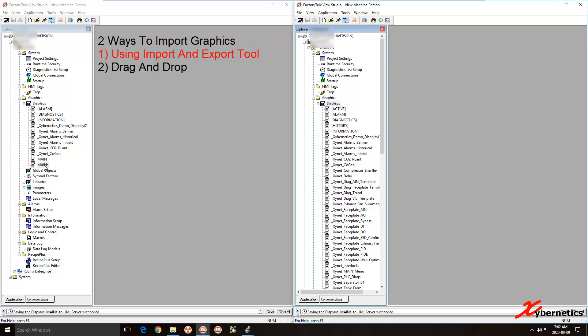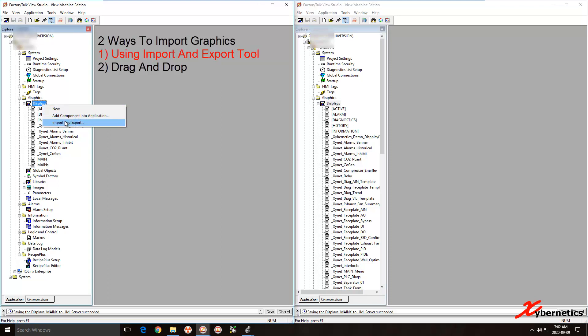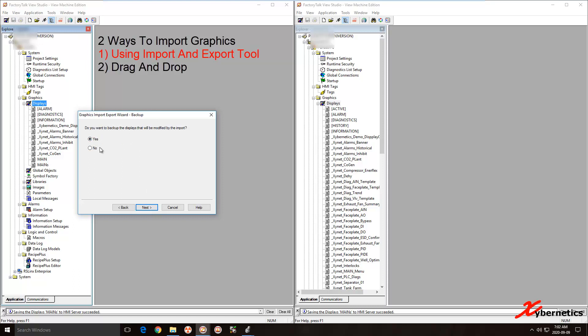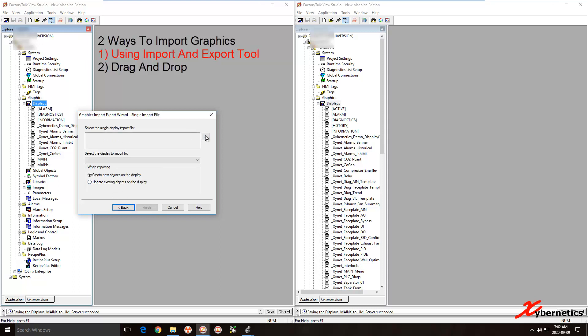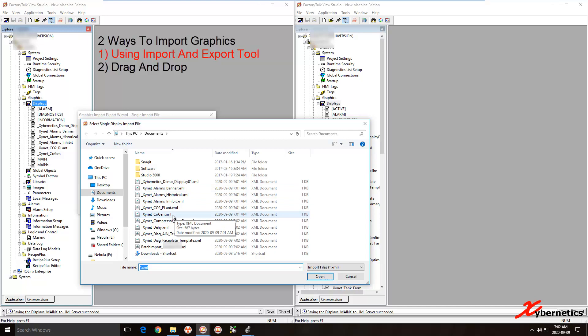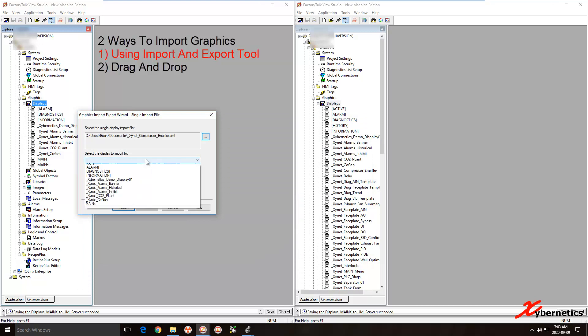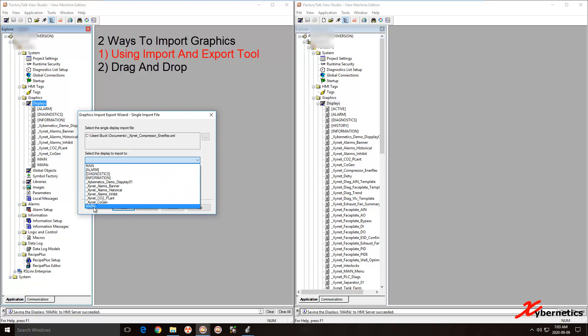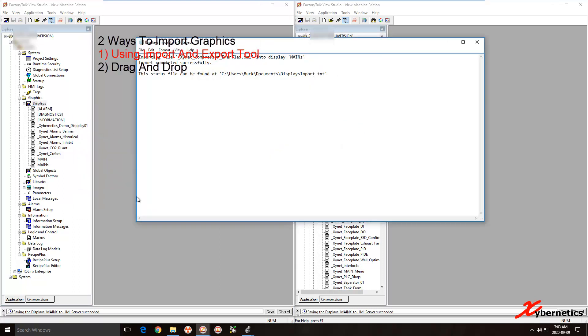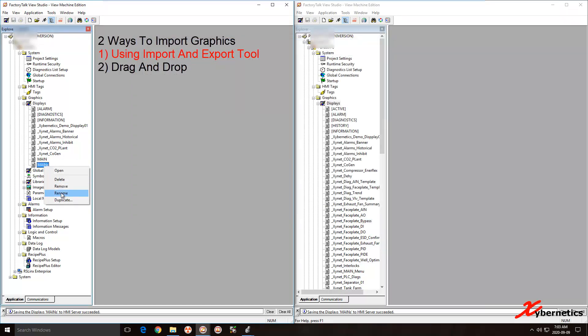You've got to duplicate a screen before you do anything. Right-click on Displays in the destination, select Import, hit Next, choose No backup, then Next. Select Single this time. Browse and select the graphic screen file you want — say Compressor Eneflex. Double-click it, then select the duplicate template you created, and hit Finish. It's successfully imported. Then just go ahead and rename that screen. That's how you do a single screen.